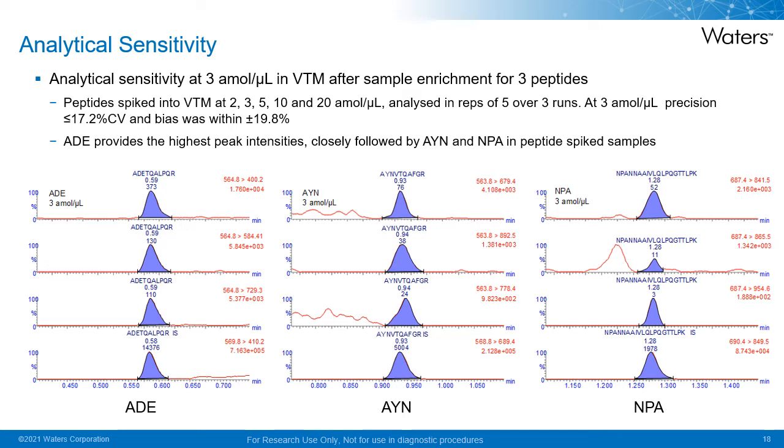The analytical sensitivity, or the LOQ, was determined following the FDA bioanalytical method validation guidelines by analyzing the three peptides at concentrations of 2, 3, 5, 10, and 20 attomoles per microliter in viral transport medium. Each concentration level was analyzed in replicates of 5 over 3 runs. The LOQ was determined to be 3 attomoles per microliter, where precision performance was less than or equal to 17.2% CV and bias was within 19.8% across all three peptides. ADE was shown to provide the highest peak intensity, closely followed by AYN and NPA, when examining peptide-spiked samples.